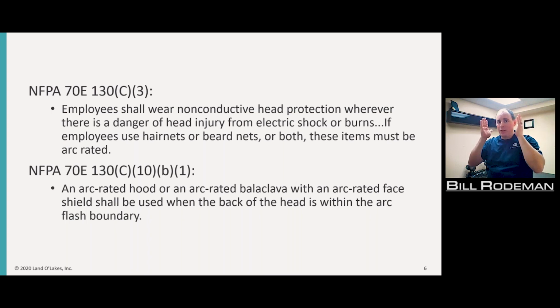If I'm wearing a standard face shield, it only comes to the sides, and if I become engulfed in the flame, the back of my head will receive a burn. This section says to make sure you wear an ARC rated hood with back protection, or wear a balaclava underneath your face shield, to make sure the back of the head is protected. It's giving you more guidance on how to actually protect employees.